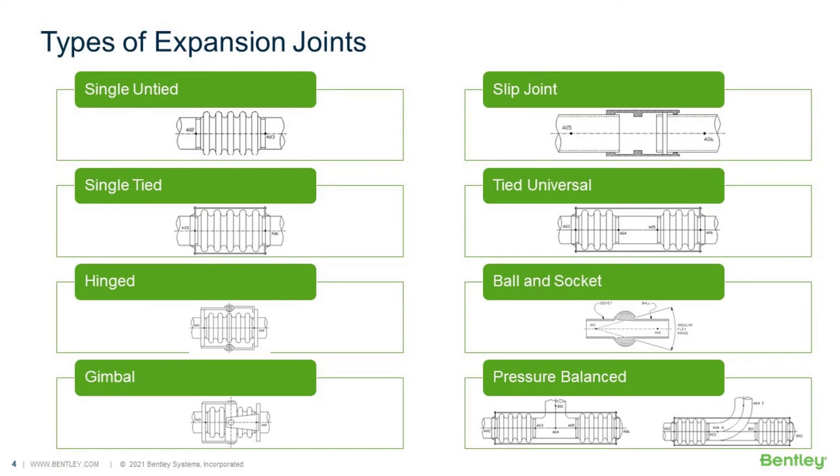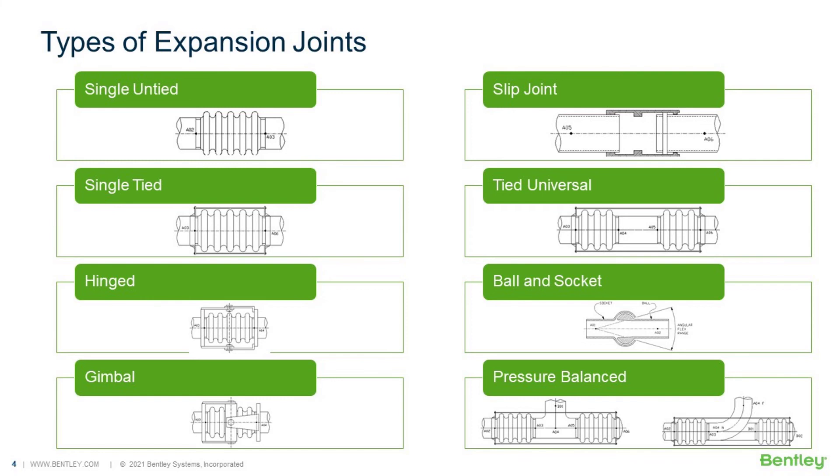We're going to explore some different types of expansion joints, but let's just first take a look at a piping model to look at thermal growth. So as mentioned, expansion joints are primarily used to manage thermal growth and there's no stopping the pipe from growing thermally. Rather, our goal is to direct it in a way that helps us to manage the stresses, the loads, and the deflections by defining a path of least resistance within our piping system. And this is going to be the most flexible area of the piping.